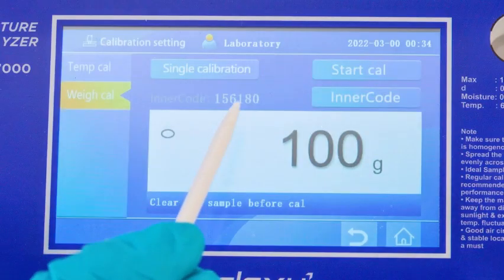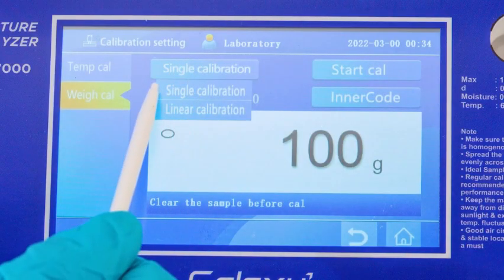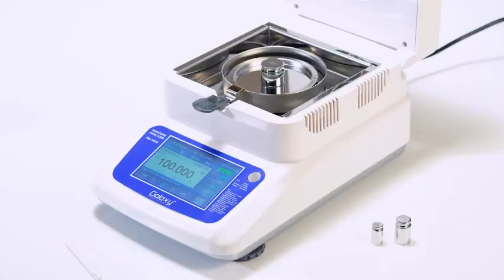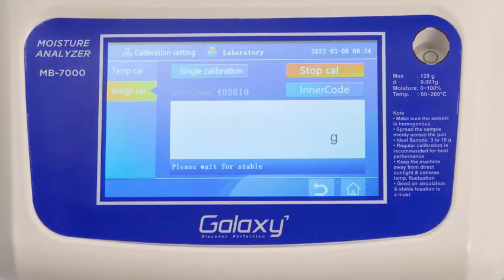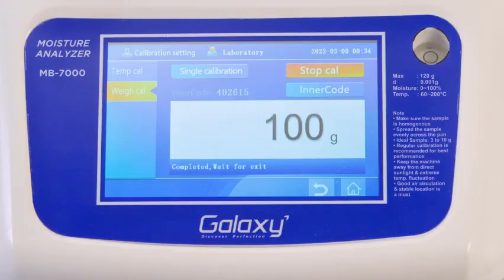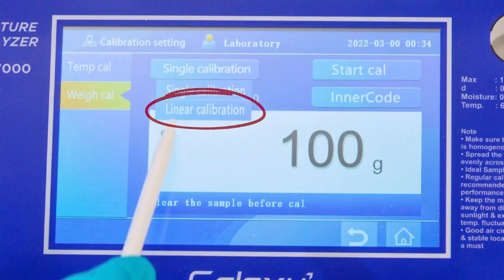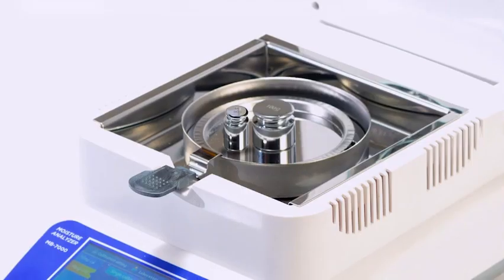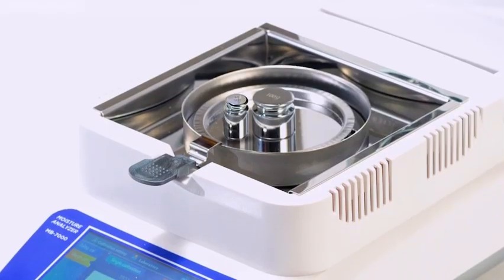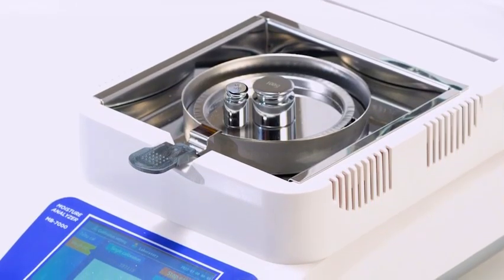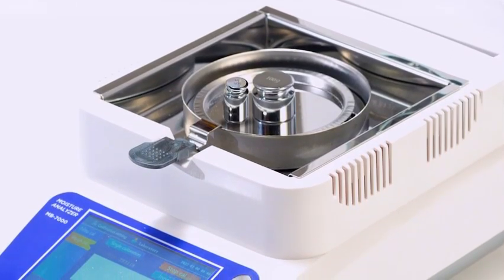In the calibration settings, you'll find two calibration modes. 1. Single calibration. This mode is straightforward and is done using a single standard weight. 2. Linear calibration. This mode is a bit more advanced, as it requires the use of multiple standard weights to ensure accuracy across a range of measurements.